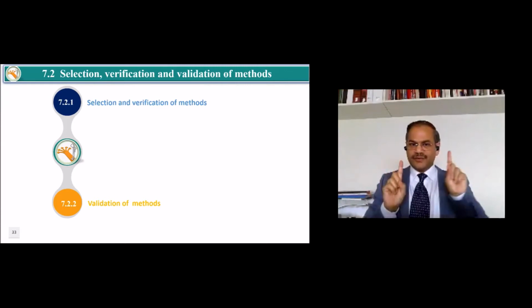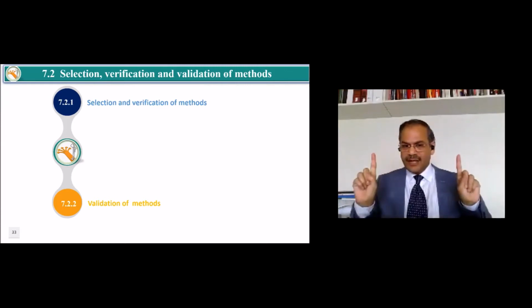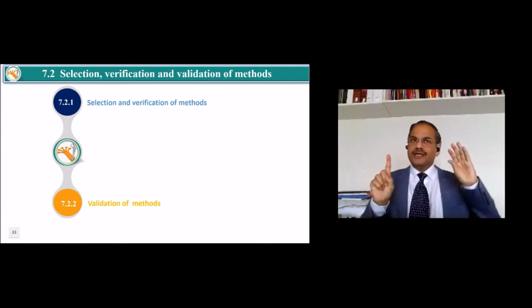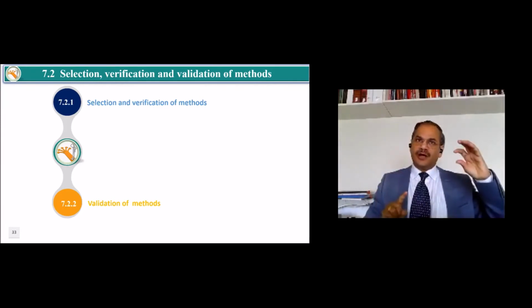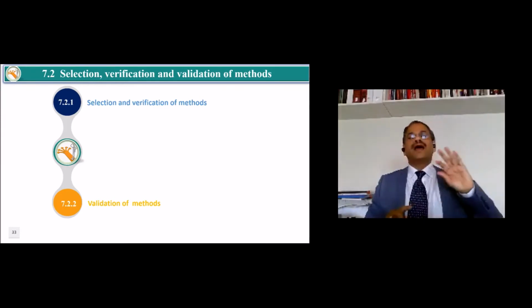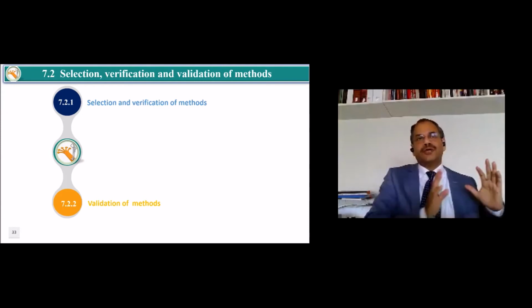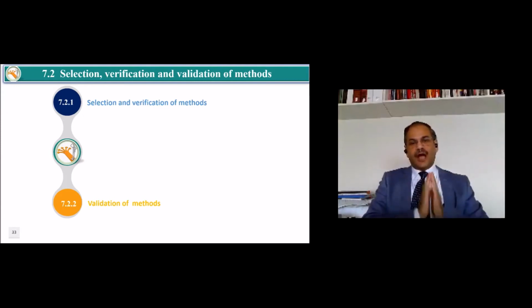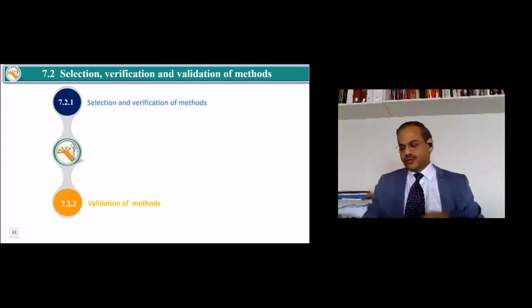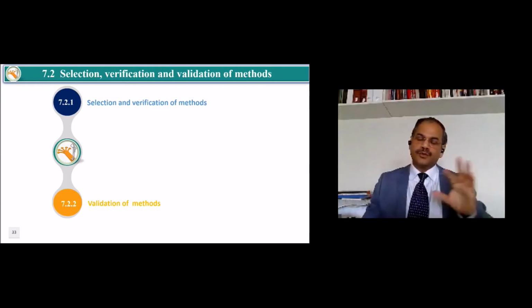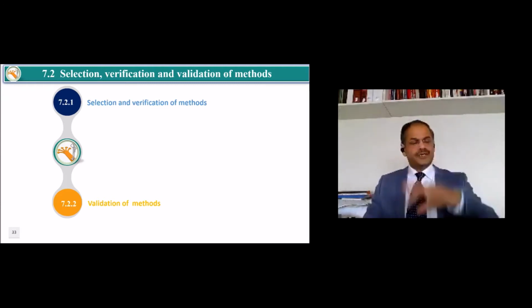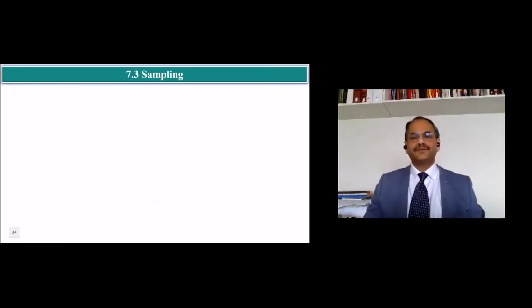So there are two different words: one is verification, one is validation. You need to know the difference between the two. If the reference method is internationally renowned, like ASTM, you need not validate the method at all unless you are going out of the scope of the method. However, if you have an in-house method, you need to validate. So 7.2 is talking about all this. If you go in the description, you can read more on that.